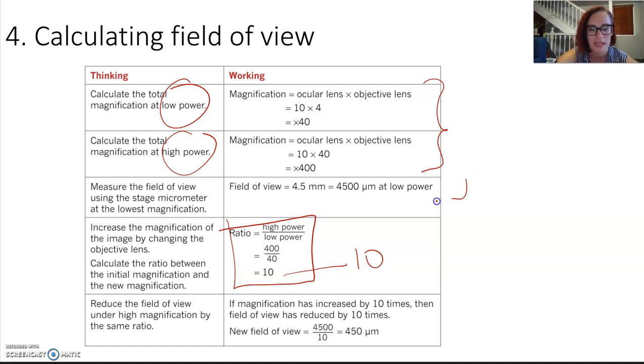We then need to use the stage micrometer. So like before, you would say how many divisions go across the diameter of the field of view, and you're going to make sure that you're working in a very useful conversion number as well there, so a unit. And then what we are going to do is take this and say, if the magnification has increased by tenfold, then what we've done is reduce. Remember, if we're moving closer, magnifying closer, then we've reduced the field of view. So we are dividing that by ten, which was our factor from up here. So take a moment, pause, and have a read.